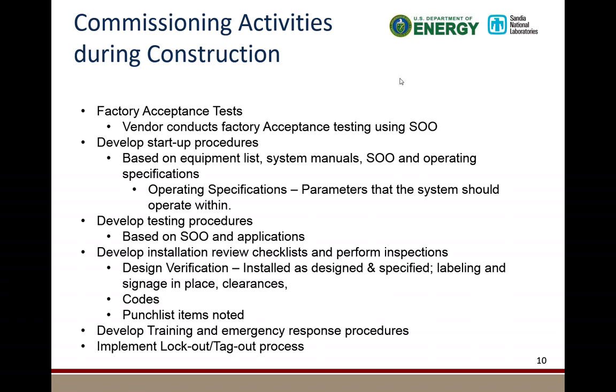And now you want to start developing your startup procedures. Once again, you don't want to wait to the last minute. You start it up now based on the equipment list, the system manuals, the sequence of operation, and then the operating specifications. Since that's kind of a weird term, I defined it there, and my definition is the parameters that the system should operate within. That would be your ambient, any pressures, any flows, anything where the system needs to operate within.